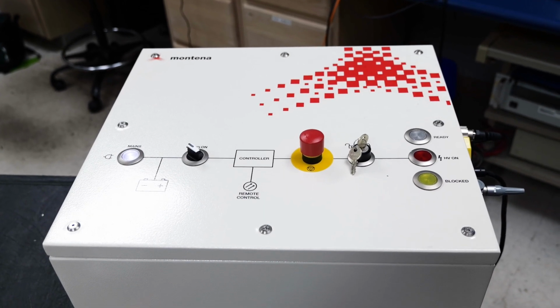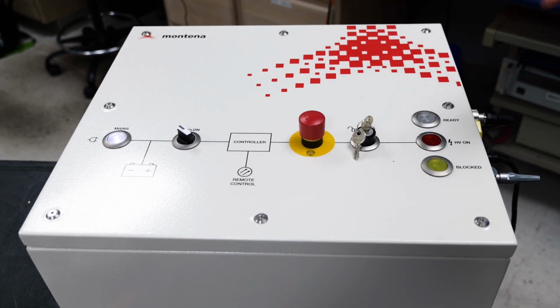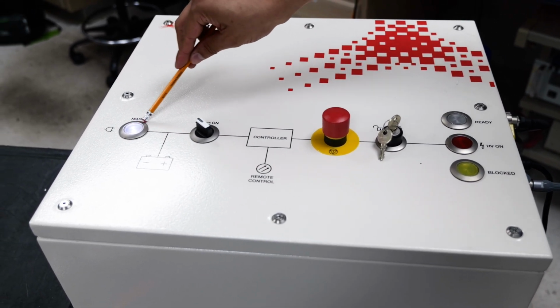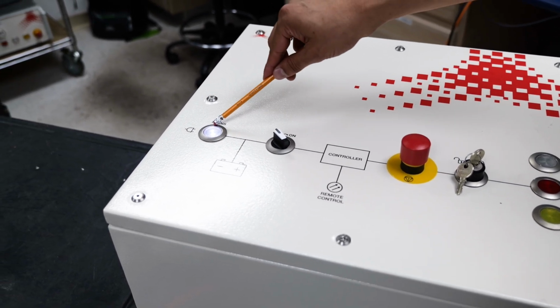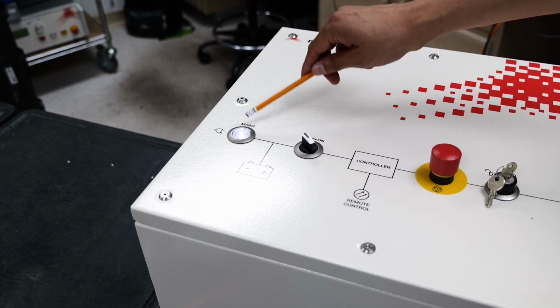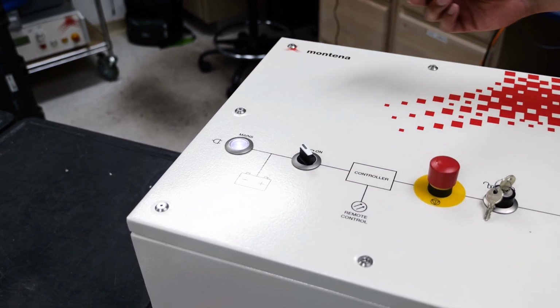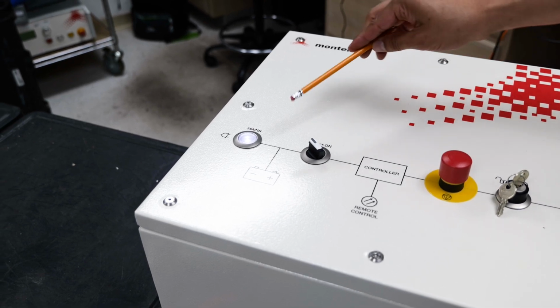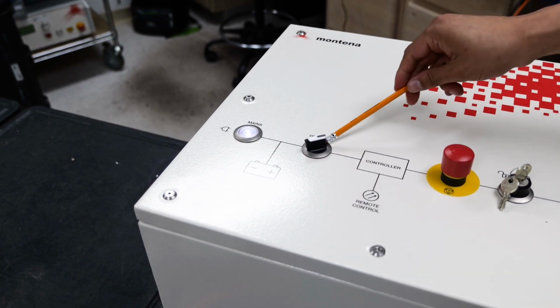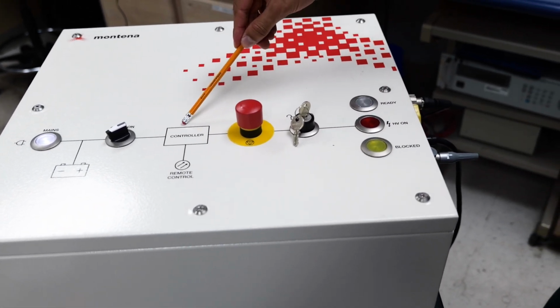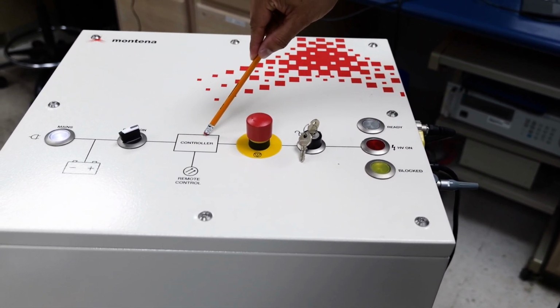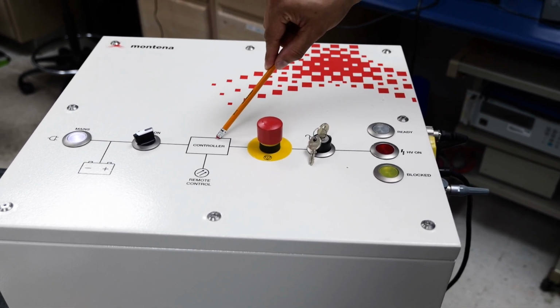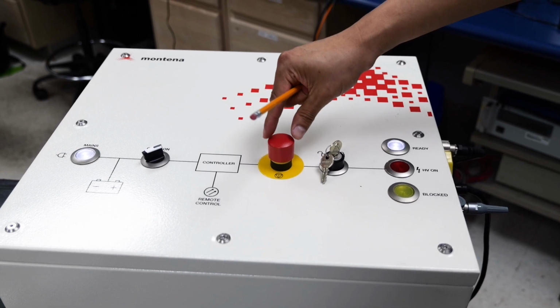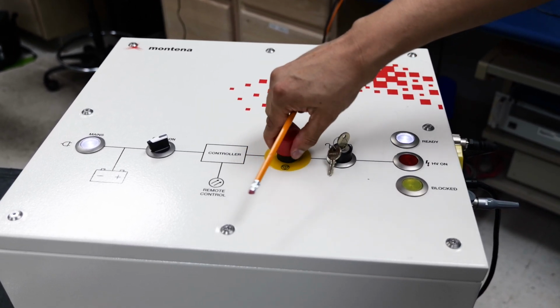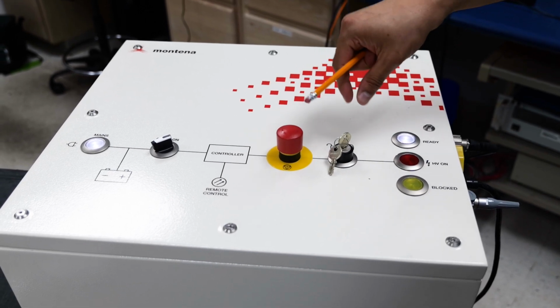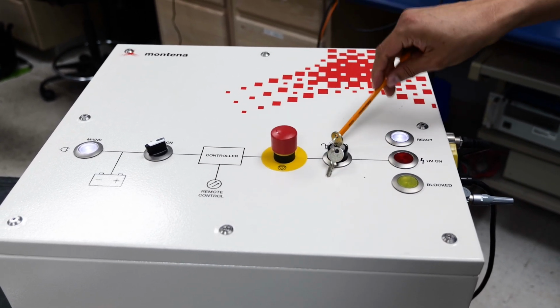So now we're going to take a look at the front panel of the pulse generator, and go over some of the connections. This light is on because we have the generator connected to the AC power cord, but it also runs off of battery, so it should last you about 24 hours using the external or the internal built-in battery source. I'm going to flip this switch to on, which now turns on the ready light. This is basically telling you that it's controlled by a PC using a controller hub that we'll get to in a minute. The generator does have an emergency stop release switch, which I'm going to reset. And it has a key, where I can flip it to enable and unlock the instrument.